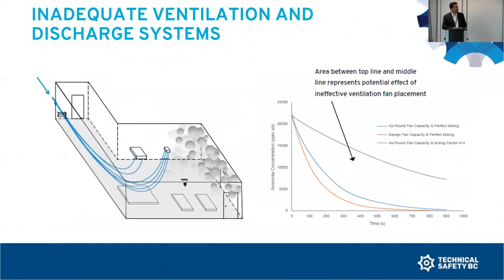Inside the room, what we found was, this image shows you the small fan that is always running, and then the large fan that's installed for leak rupture scenarios. So when there is an ammonia leak, it comes on. This large fan was installed directly within the established airflow. So it effectively did nothing to help evacuate the room. And that's exactly what we saw on the roof, is that this did nothing.